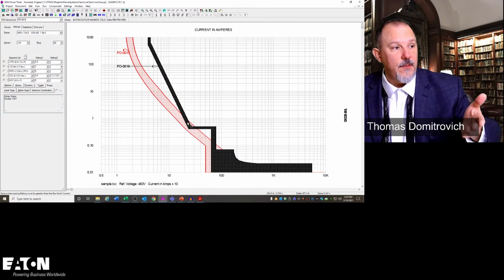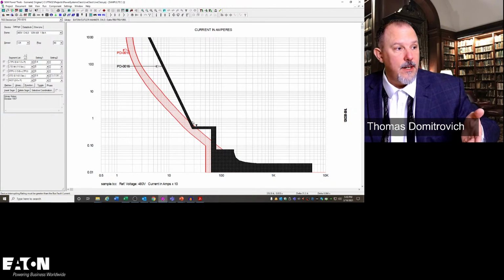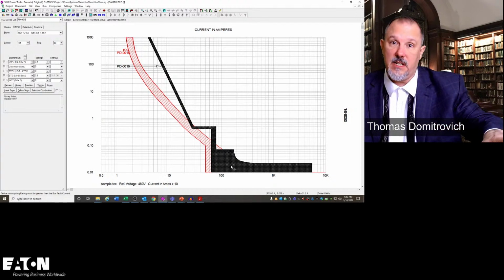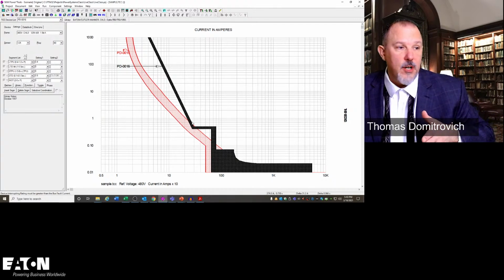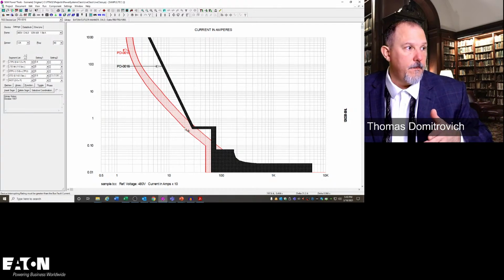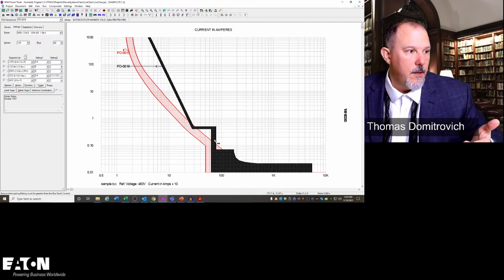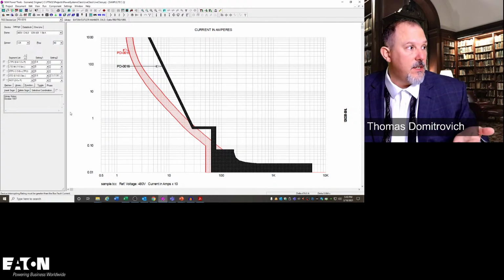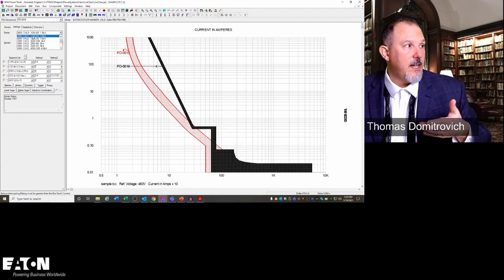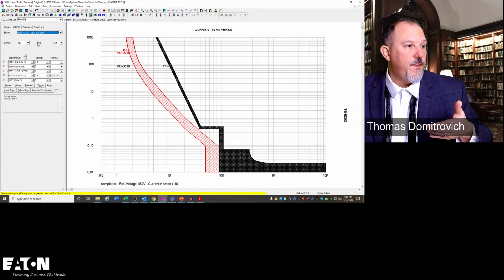So if I tried to selectively coordinate this, I couldn't in the overload region, let alone the instantaneous region for the very high fault currents, because I've got an overlap of curves here. So what is my solution? In this case, the only solution I have is to increase the frame of this circuit breaker. So I take it from 125 amps to 250.